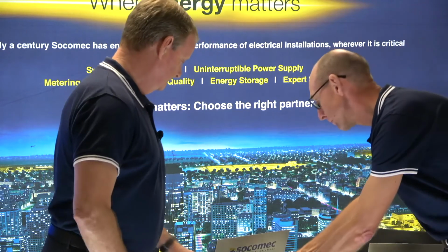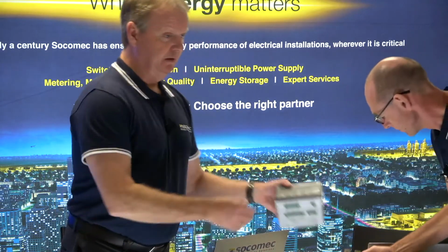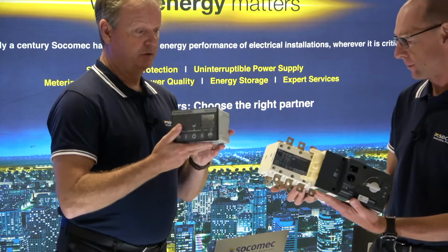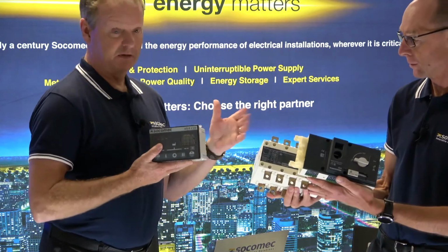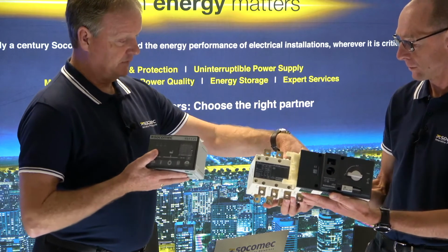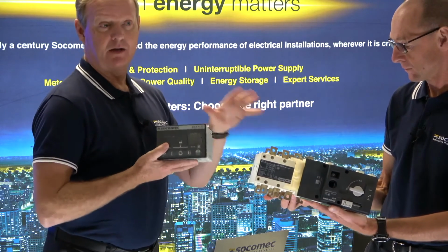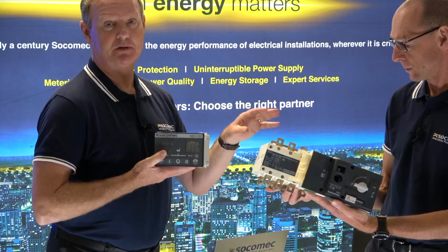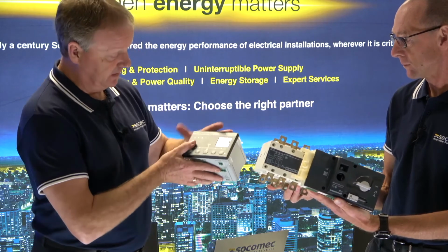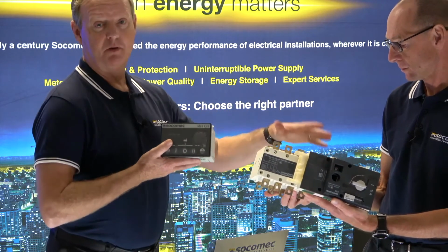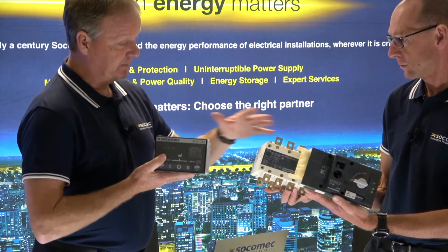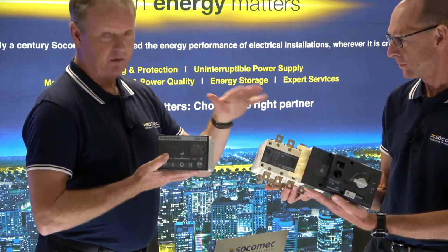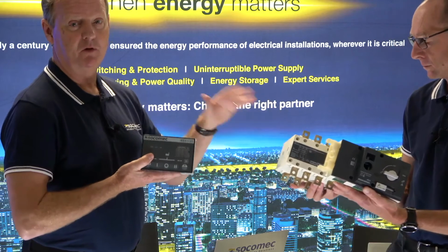What we're going to show you here is a two-part transfer switch and controller. This is not allowed under BS 8519-2020, even if it is the same manufacturer. In this case this is a Socomec one, but you can have different manufacturers. Under this issue, you cannot have this for BS 8519 for life safety services.